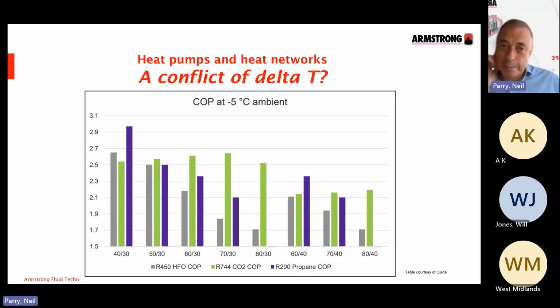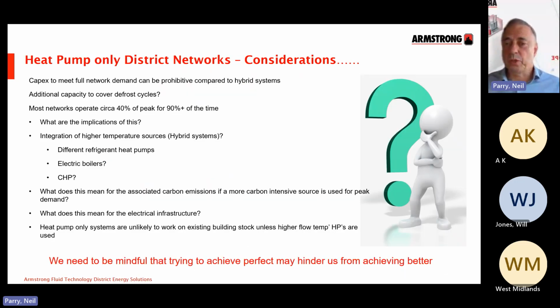So if we're looking at heat pump only networks, there are some considerations we need to think about. The capex can be problematic if we're going solely with heat pumps for 100% of the demand, because we have to think also about defrost cycles, and do we need to cover for that somehow? So additional capacity in there to cover for those cycles. So it's quite difficult. And as I explained, if we're looking at a hybrid system, with only 40% of the demand coming from heat pumps, we can hit what we need to hit for our renewable integration. So we need to think about that integration. What does that mean for the associated carbon emissions?